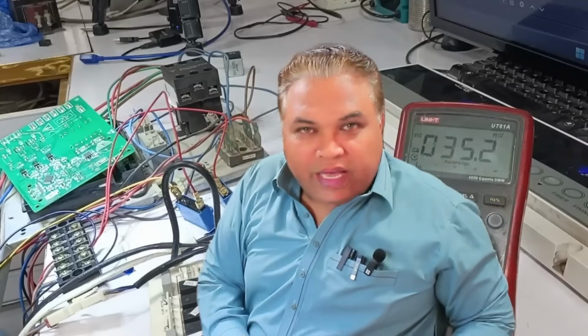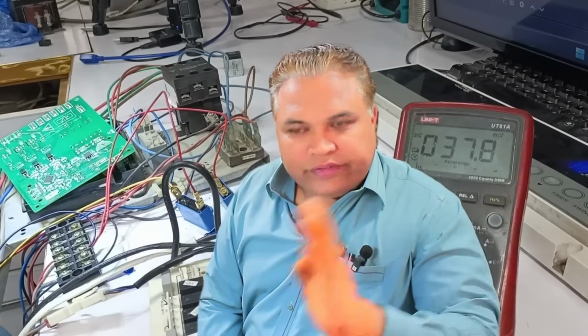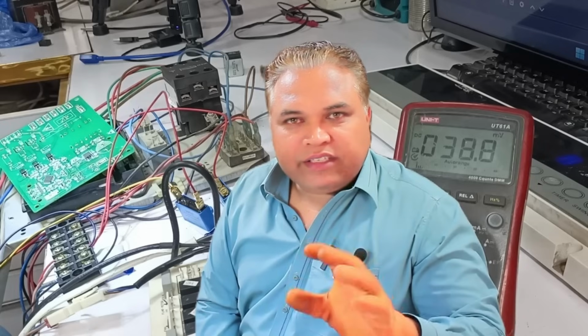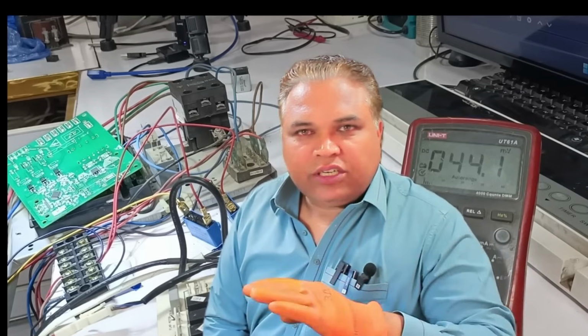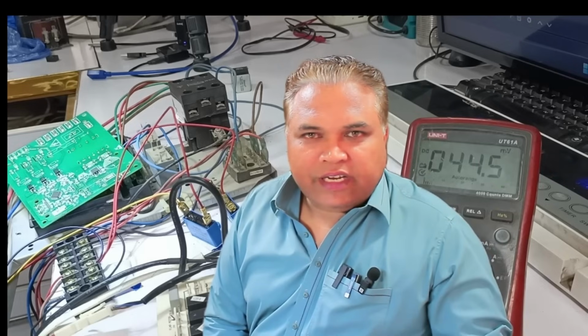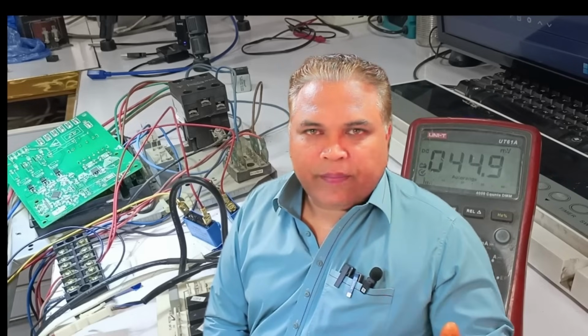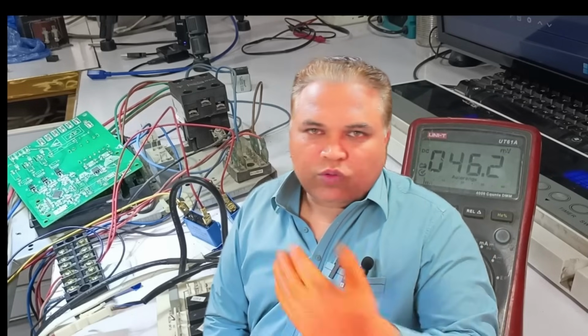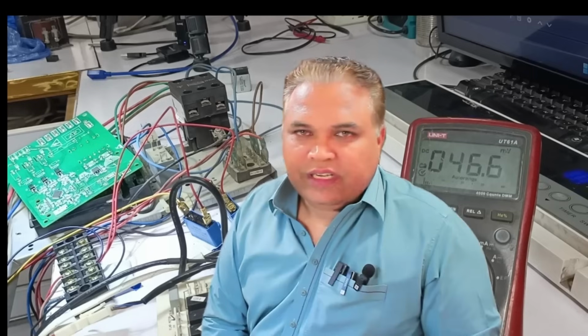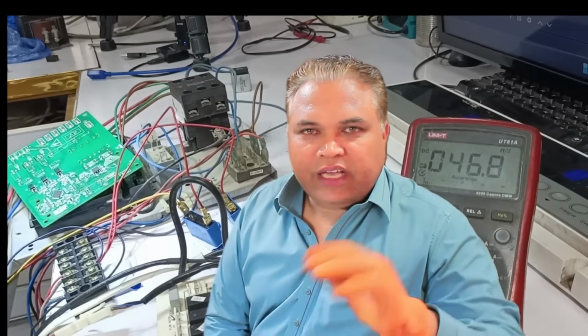As I explained earlier, this circuit controls only 2 main functions. The first main function is to detect the signal, which allows the system to confirm whether all 3 phases are properly present or not. If even one phase is missing when the unit turns on, there is a high risk that the compressor could get damaged. To prevent this, this detection circuit has been added. The second function of this circuit is to activate the relay and send a signal to confirm that there is no high-pressure issue and that the system can operate smoothly.